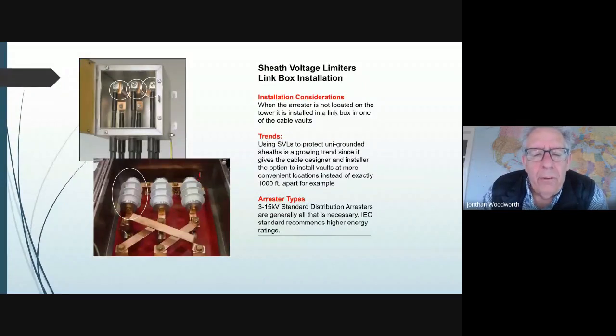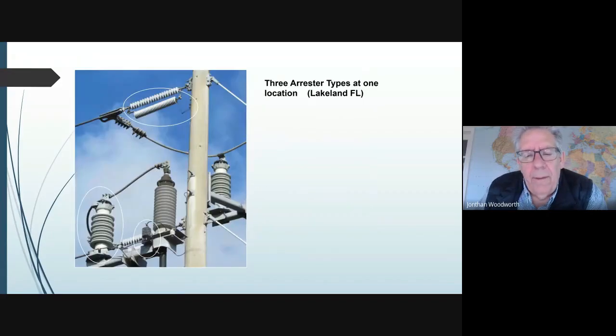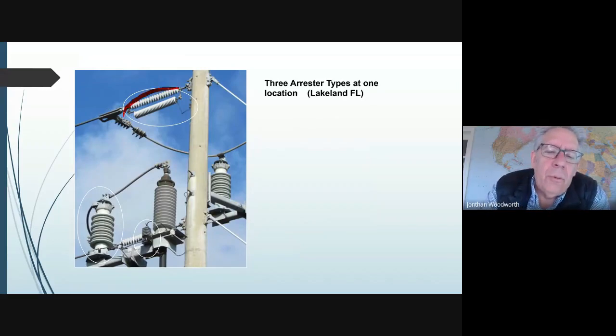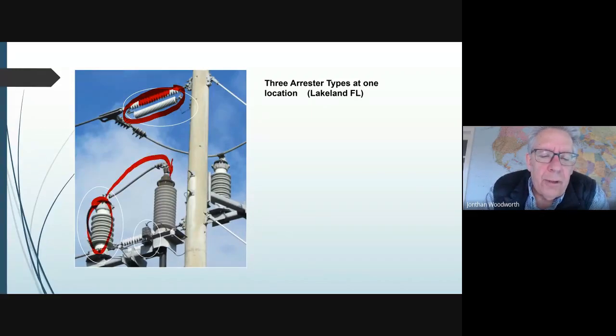Down underground, there's some vaults sometimes, and you'll see sheath voltage limiters also underground. Here's another transmission line arrestor that's protecting this insulator from ever flashing over. So the purpose here is never to have a flashover on that insulator. This arrestor is protecting the inside of the cable, and this is the sheath voltage limiter protecting the sheath.